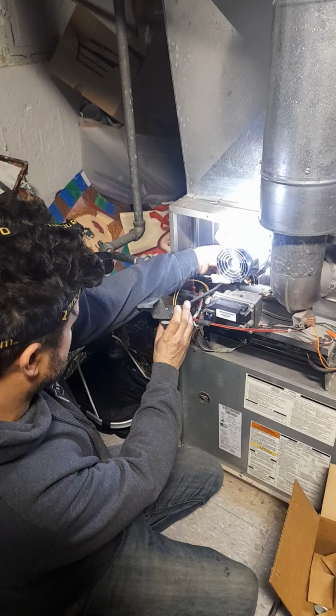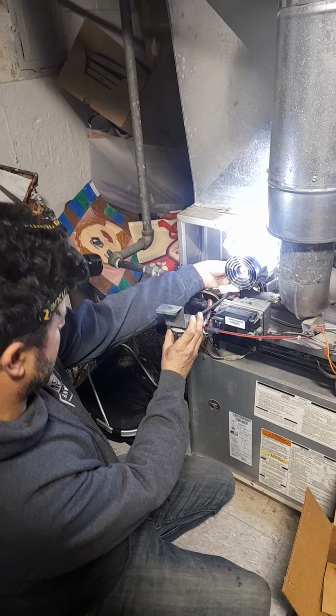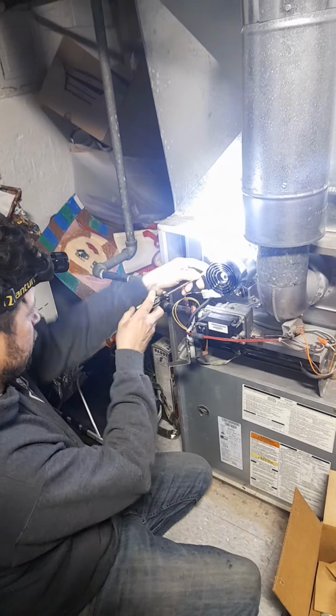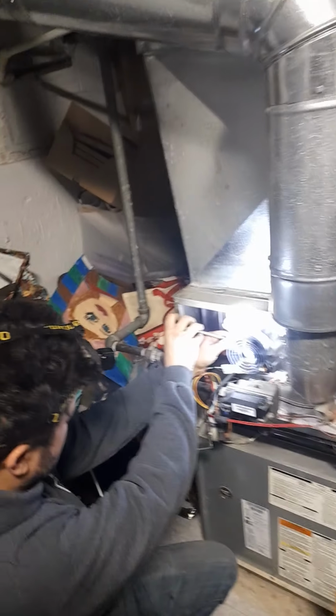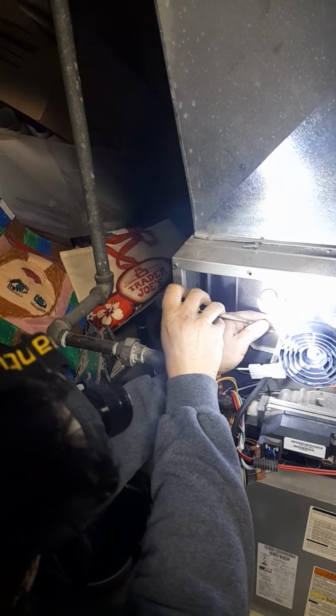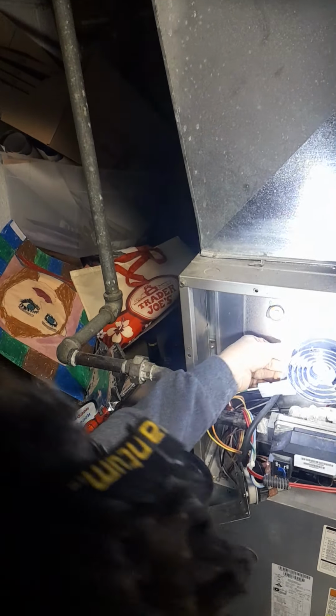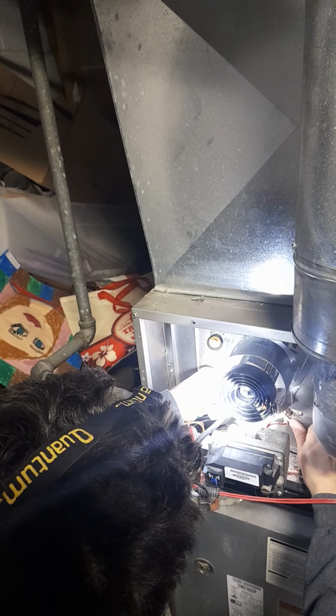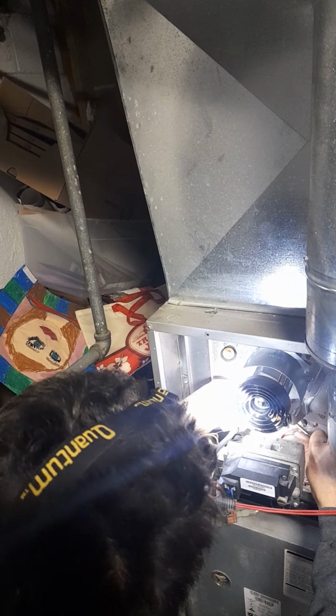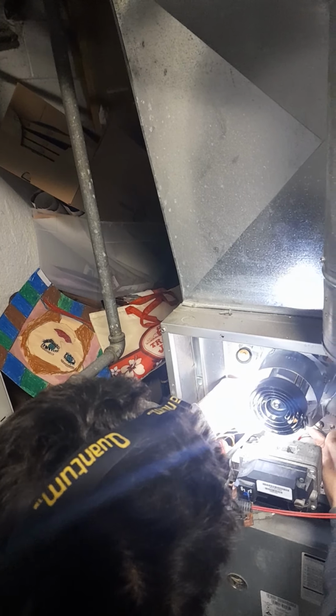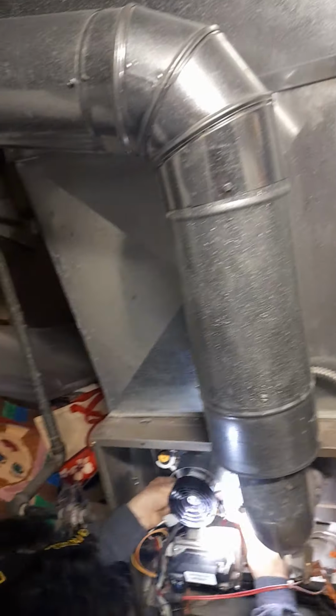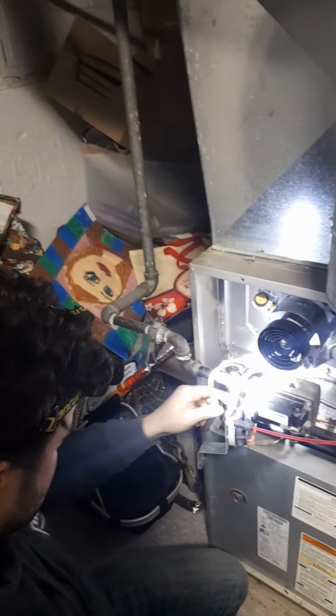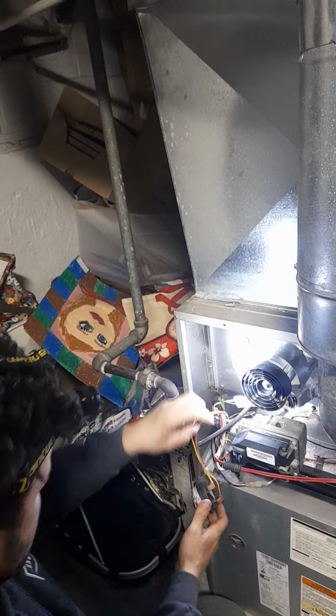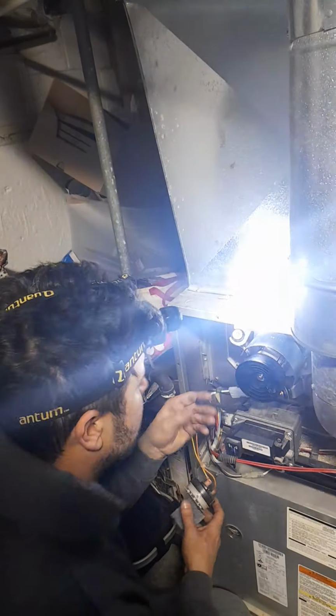All right. So that was that, and now we get this pressure switch back to the spot. Although, we should probably check to see if any water's accumulated in this pressure switch. You can't pull these silicone tubes off. The more you pull, the harder they get to get off. So what you do is you got to push it off. That's why I'm sticking this on. This one might be barbed, actually. I could have just done the, what do you call it, side. Pressure switch side. This is not barbed, but no water. I'm sucking in. There's no water. No, because condensate forms, you know.